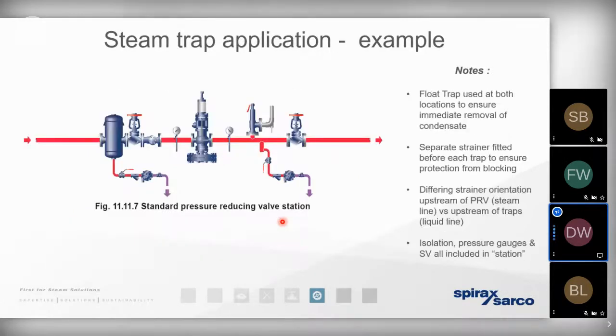Other areas where traps should be used are at the bottom of those steam separators, ahead of pressure reducing valves or control valves, to ensure that at any point where steam or condensate could potentially become trapped, it is allowed to be drained away and dumped to waste, or taken away back to the boiler house where it can be reused efficiently.